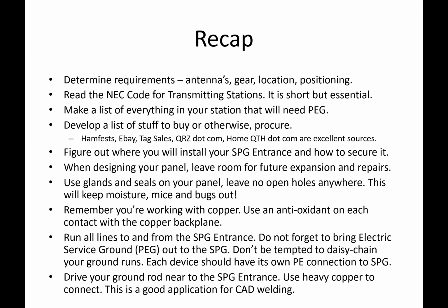The one thing I was wondering if you were going to bring up is checking around your water meter that you have a good ground if you're grounding to a copper pipe in the home, which many people do, and finding out that they have not put the jumper in across the water meter - if you wanted to address that.